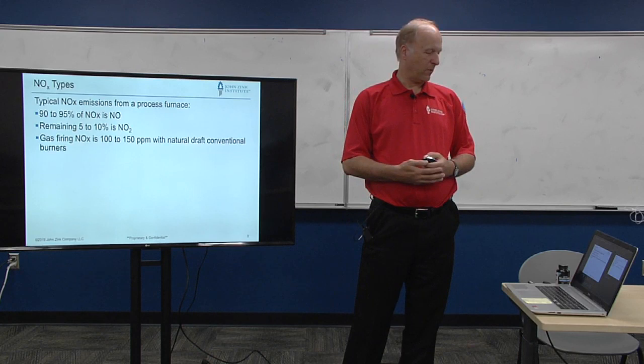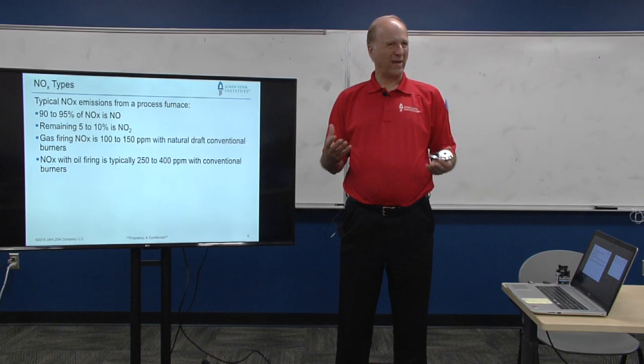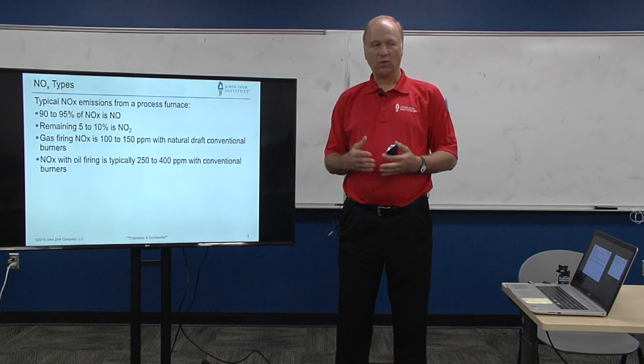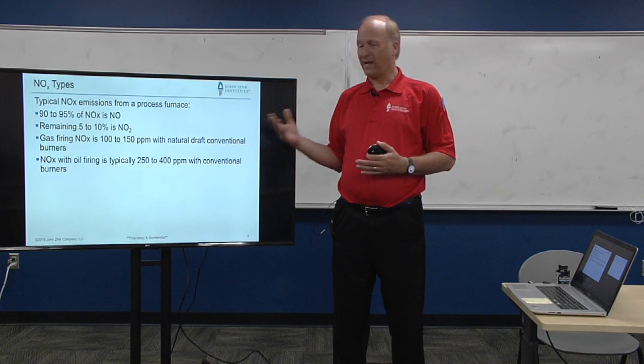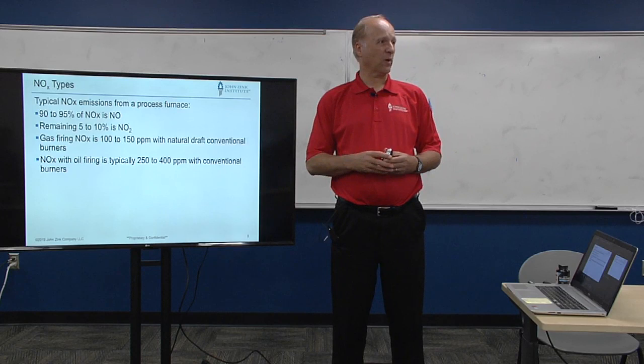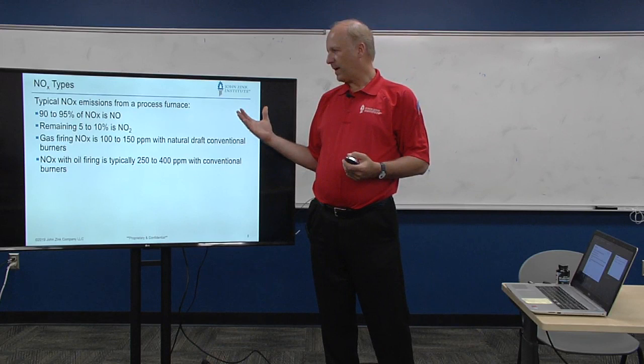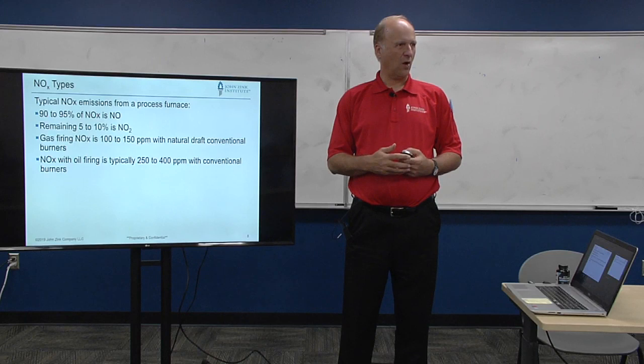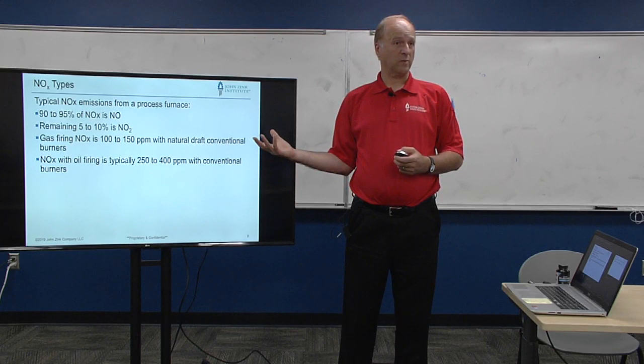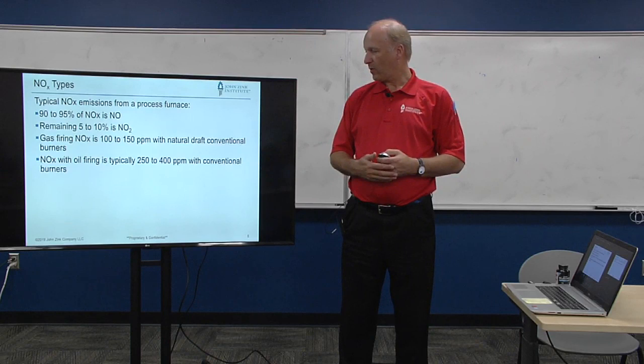In some countries using older technology, 100-150 ppm is a common range. Oil firing usually generates more NOx because oil often has organically bound nitrogen as part of it. That nitrogen — combined with hydrocarbons rather than as N2 — breaks off very easily to make NOx. So when making guarantees on an oil-fired system, we need to know how much organically bound nitrogen is present. Today in the U.S., very few people fire oil for industrial processes because it makes too much pollution and it's too expensive to clean up — cheaper to fire a gaseous fuel.